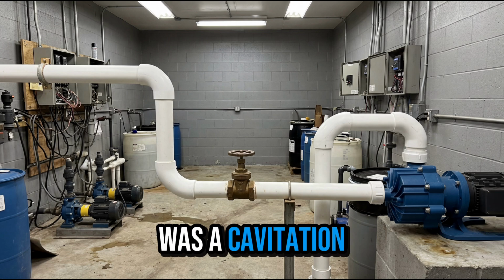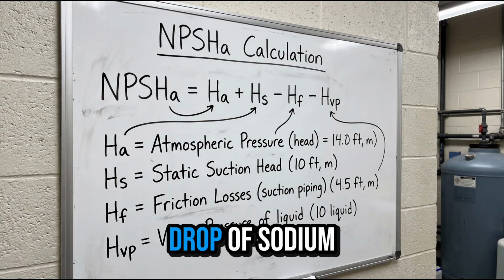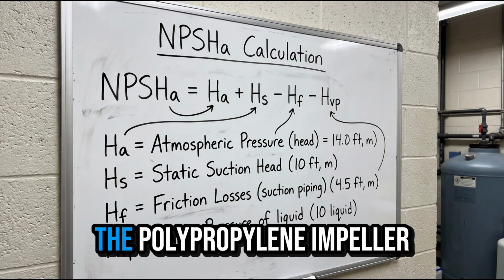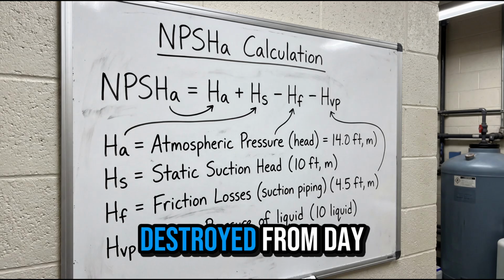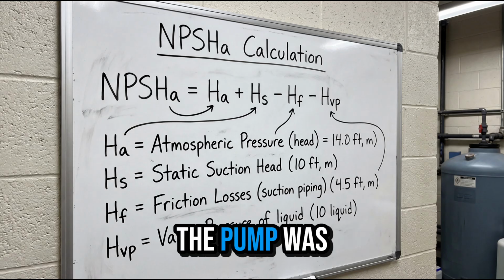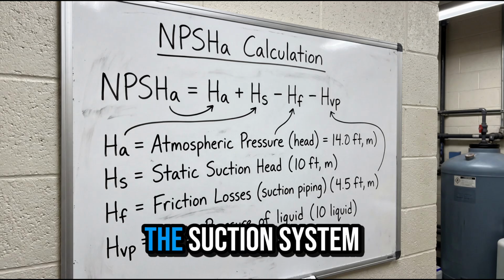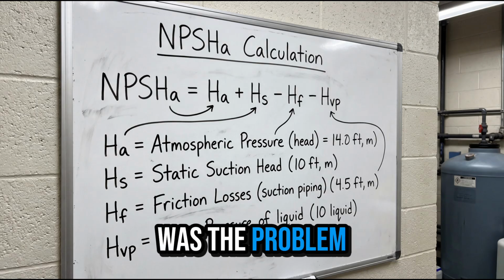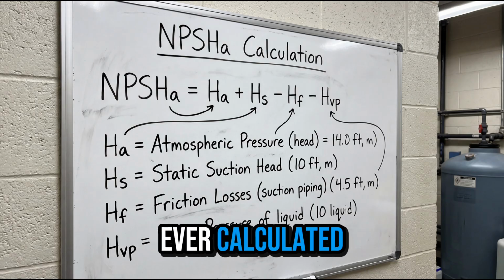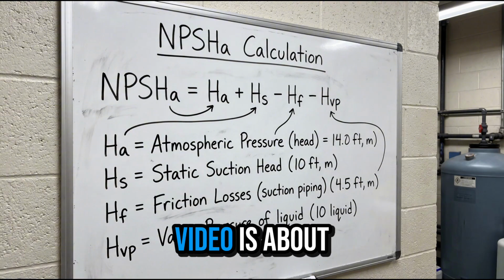Every startup was a cavitation event before the impeller ever moved a drop of sodium hypochlorite. The polypropylene impeller face was being destroyed from day one. The pump was not the problem. The suction system was the problem. And nobody had ever calculated NPSHa. That is what this video is about.